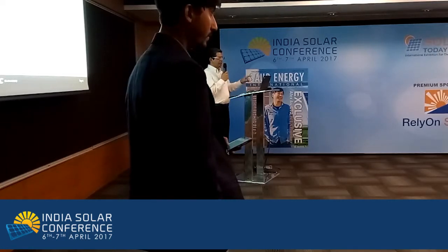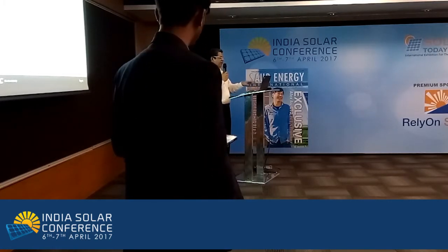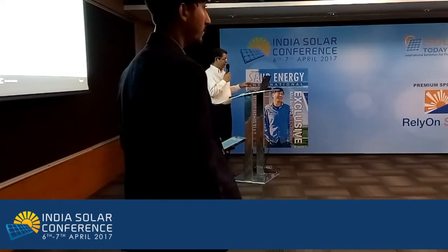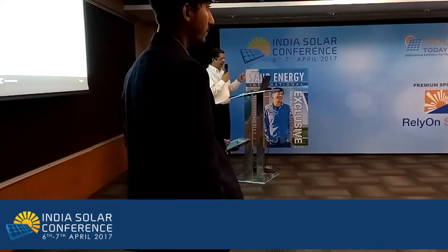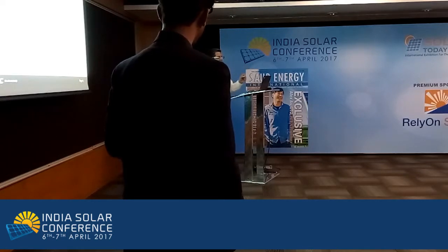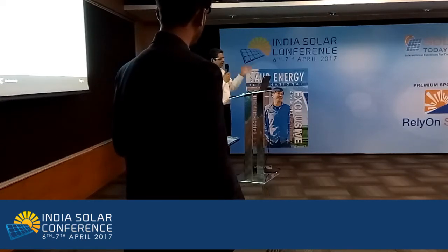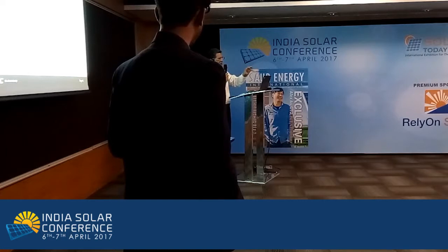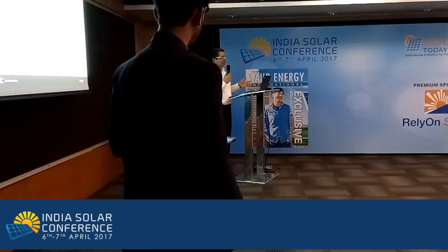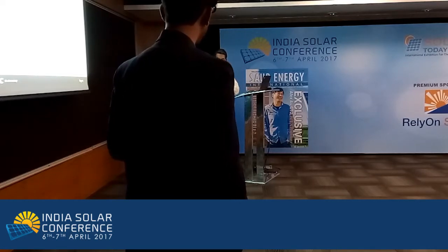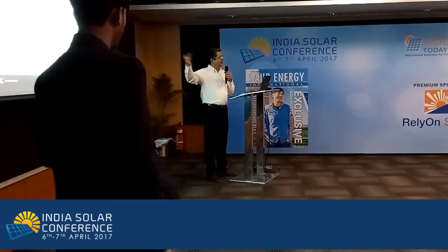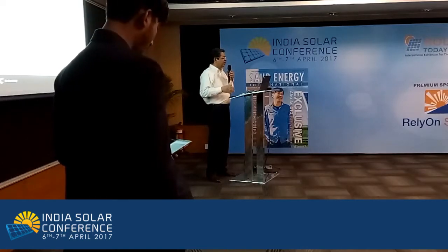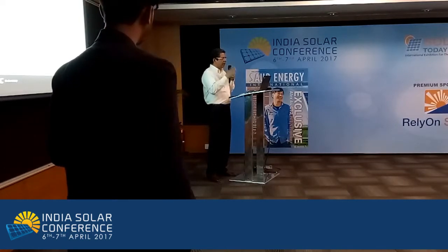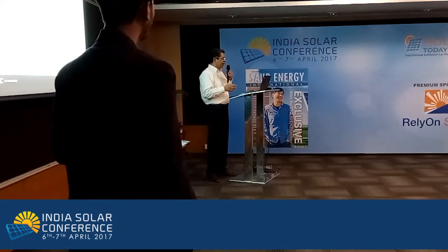Yeah, again, you're looking at a 20 to 25 years marriage here. Personally, I'm not fully convinced of electronics itself, in the sense that if the entire product is mostly electronics, I don't believe it's going to last 20 to 25 years. I would rather have a huge central inverter, where we have small electronics which we will replace. It will cost a little bit. But for the string, the entire inverter has to be replaced. So anyway, there are two sides of the same coin.